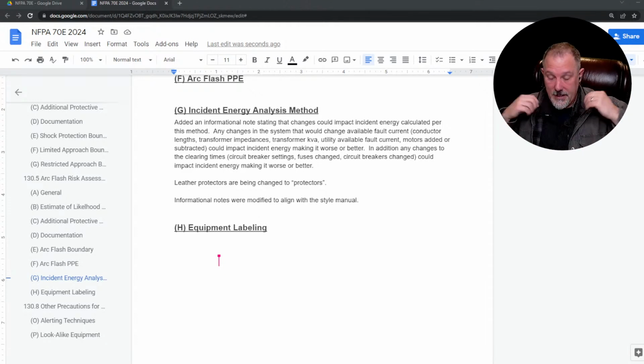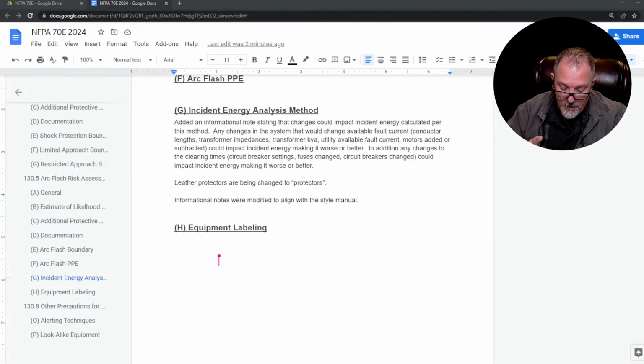The only difference I can find is in table 130.7(C)(15)(c), arc flash PPE category 1 does not require a balaclava. And remember, arc flash PPE category 1 goes up to 4 calories. If I had 2 calories calculated, I would be in table 130.5G and I would need a balaclava. But I could wear PPE category clothing with an arc rating of 4 and not have to have a balaclava if I'm using the table method. That's the only difference I see between the two.